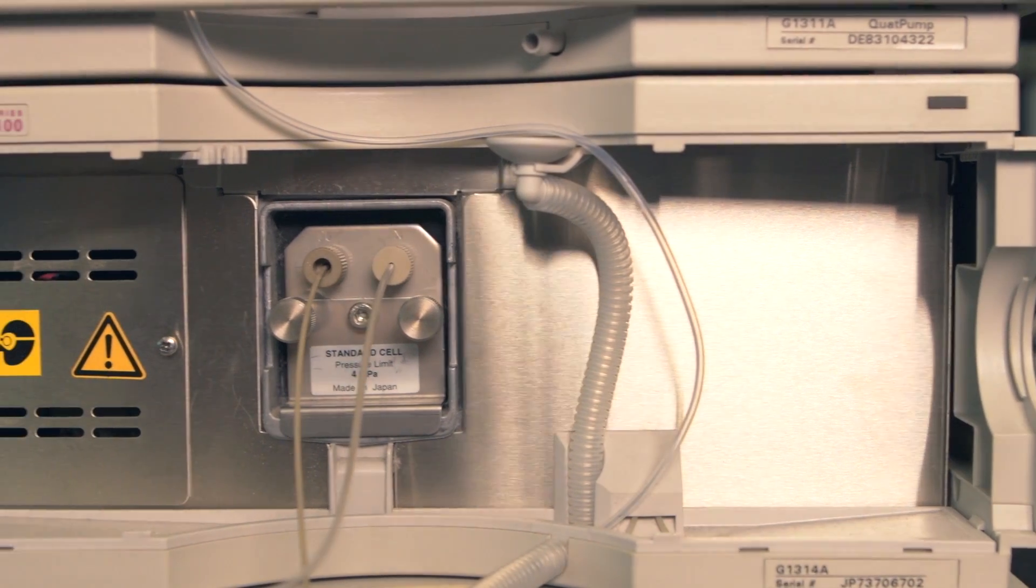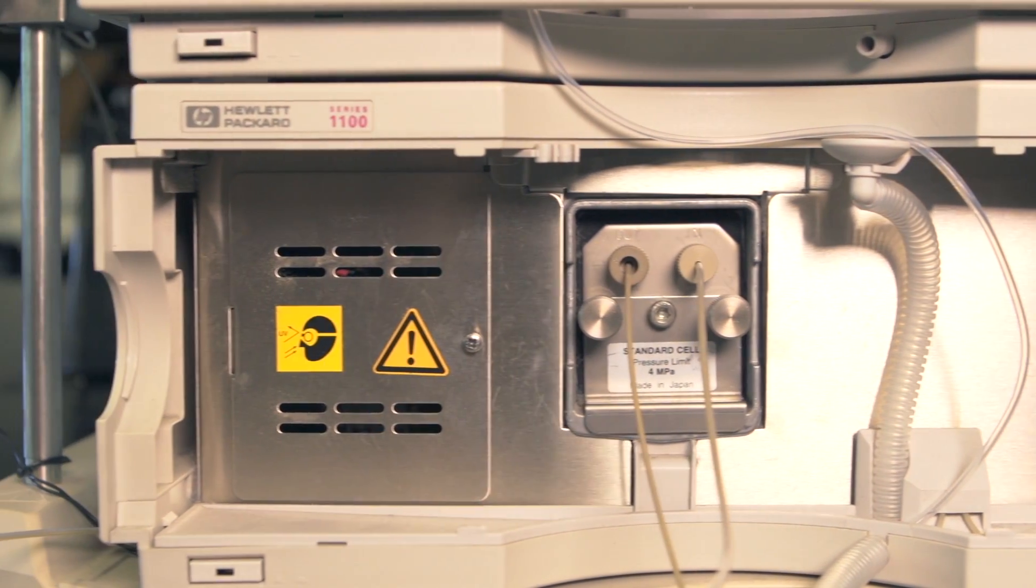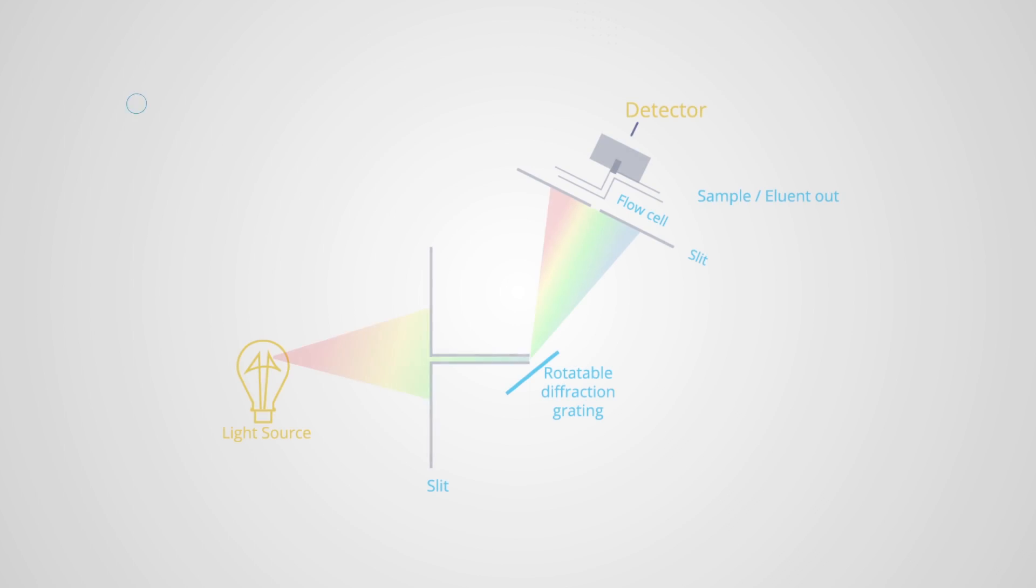With each component now hopefully separated from the others, they make their way to the detector module, which measures the properties of the column effluent as a function of time to generate a chromatogram. The detector module in this instrument consists of a deuterium lamp, flow cell, and a variable wavelength UV absorbance detector.